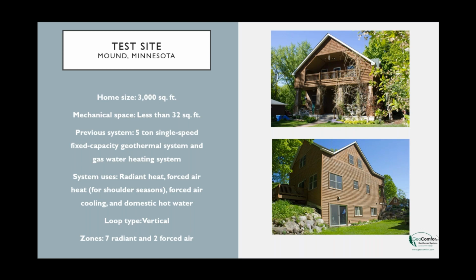So what we replaced is we got rid of the 5-ton single speed, put in the 5-ton variable speed, the new all-in-one system, and then we put in the indirect tank, and we're heating the domestic now off of the geothermal. Okay, this home again is all radiant heated. There is some forced air heating for the shoulder seasons, and we're also doing forced air cooling. It is a vertical loop field, and we have a total of 7 radiant zones and 2 forced air zones, and now doing the domestic hot water.